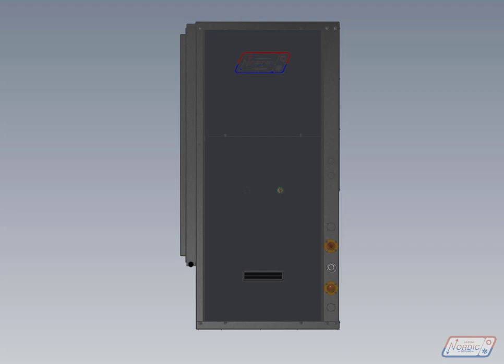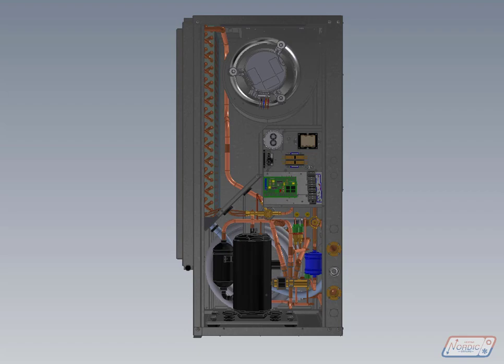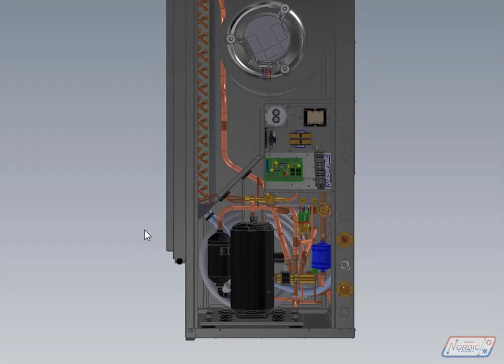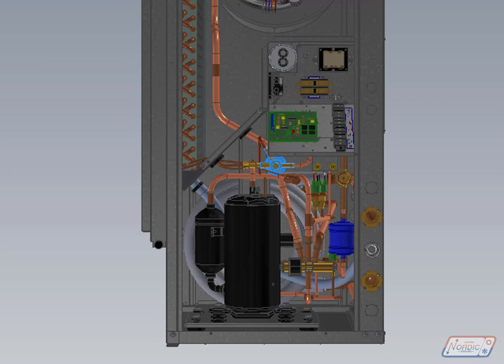The line components will seem very familiar to those who work with heat pumps. We have a balanced port externally equalized TXV to control superheat regardless of the operating conditions. We have a reversing valve to provide heating and cooling. We have a sight glass for moisture detection and refrigerant charge indication. We've got a filter dryer for moisture and particle removal. And we have easily accessible high and low refrigerant access service ports on the unit as well.